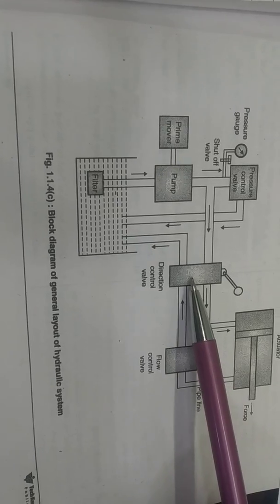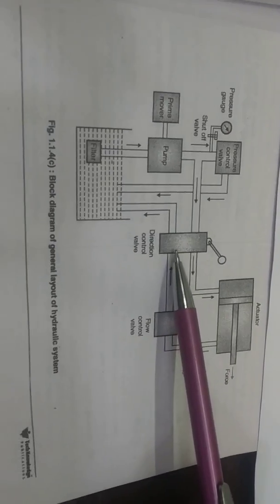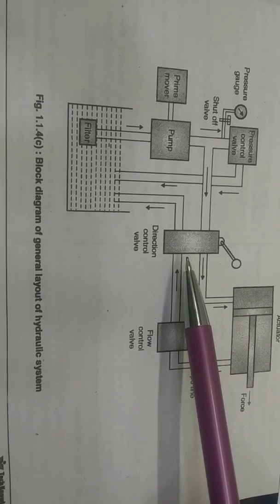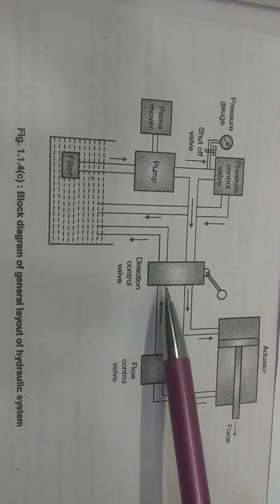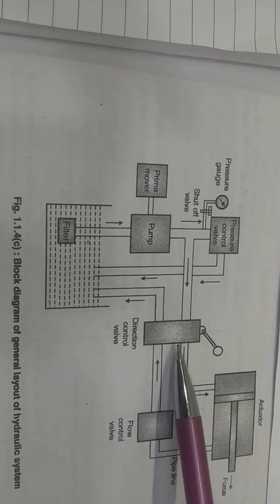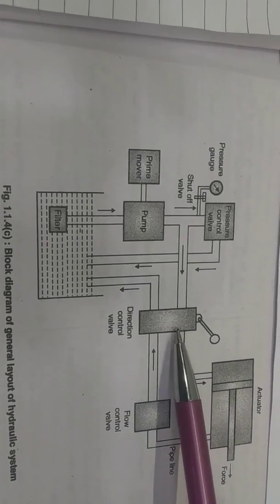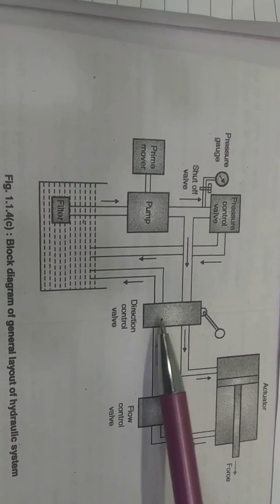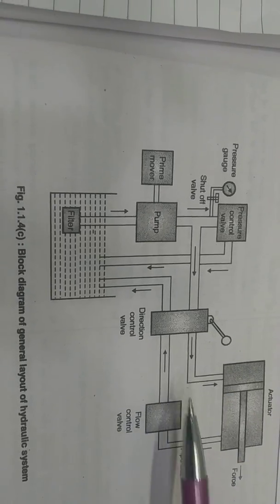The next component of the layout is the direction control valve. There are different types of direction control valve — it may be 3/2, 4/2, or 5/2. As per the application we can use the appropriate direction control valve. The main function of the direction control valve is to change the direction of the flowing fluid inside the circuit, so that we can obtain the movement of the actuator in different directions.